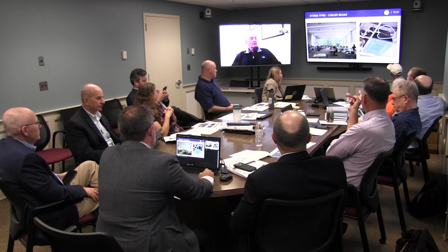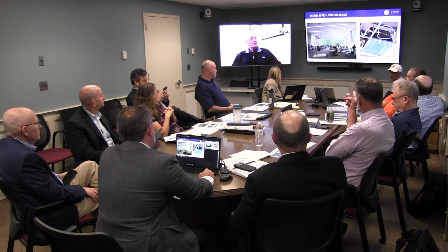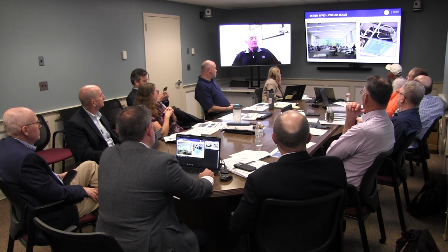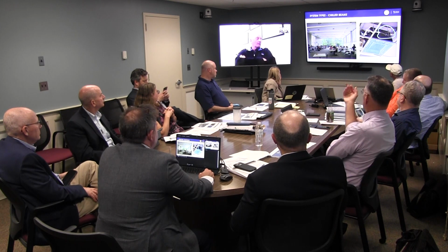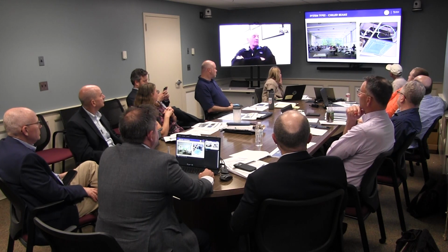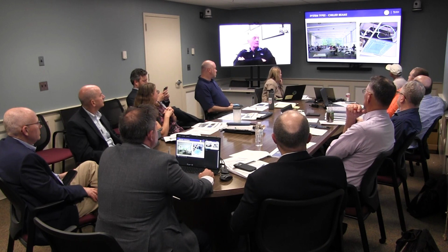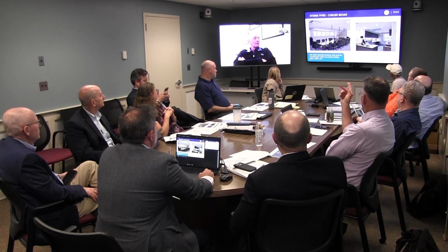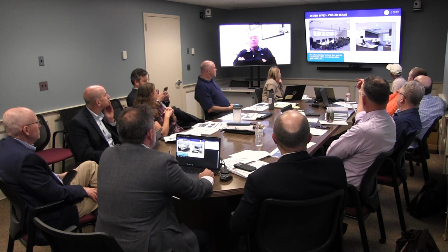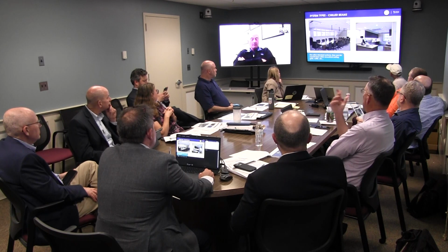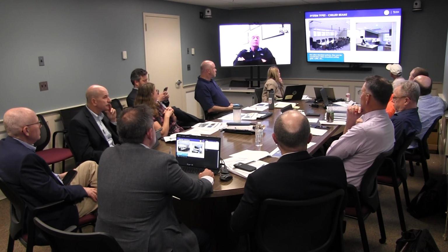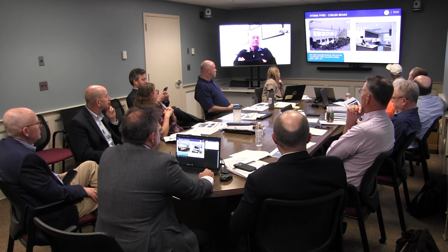This picture is actually chill beams in the center, the induction beams, and along the perimeter there's one-way blow beams, in a kind of a cafeteria collaborative type space with a very high ceiling. So the options are very flexible. And then you can also put them in conference rooms, and there's a chill beam in the offices. So in the admin and smaller offices, these are very adaptable to smaller type spaces. And each of these beams gives you individual control of your environment, each space.